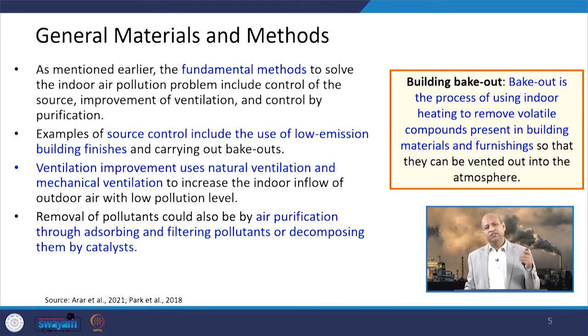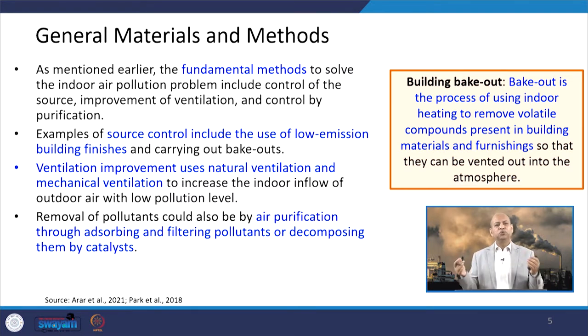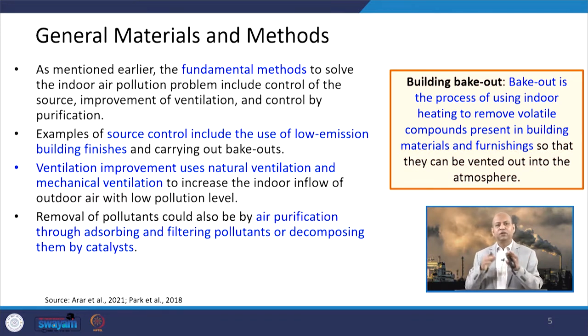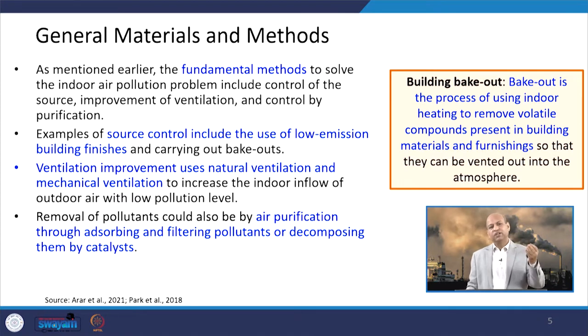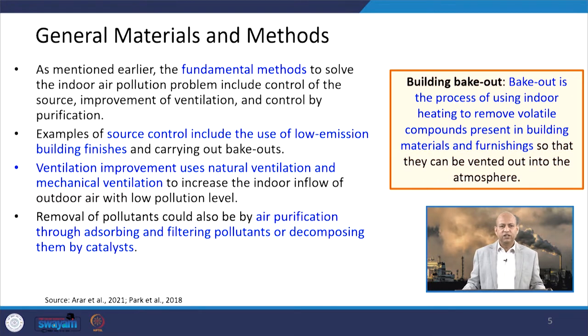Ventilation improvement can be achieved through natural ventilation or mechanical systems such as air conditioning or exhaust fans, which increase the inflow of outdoor air. However, we must ensure outdoor air is cleaner than indoor air; otherwise, ventilation can deteriorate indoor air quality. If outdoor air is clean, ventilation works well; otherwise, air purification devices using adsorption, filtration, or catalyst-based decomposition can be used to remove pollutants.